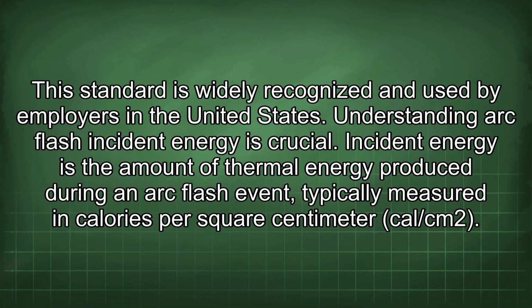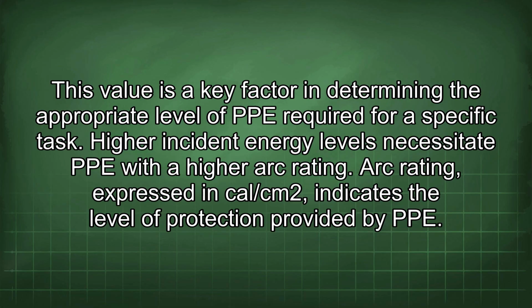This standard is widely recognized and used by employers in the United States. Understanding arc flash incident energy is crucial. Incident energy is the amount of thermal energy produced during an arc flash event, typically measured in calories per square centimeter (cal/cm2). This value is a key factor in determining the appropriate level of PPE required for a specific task.